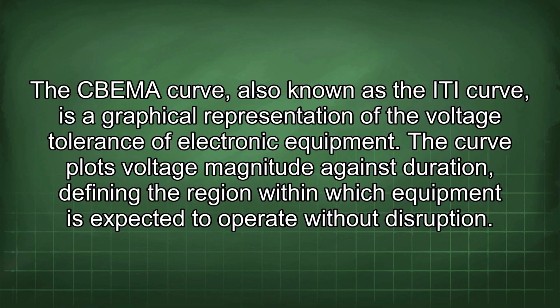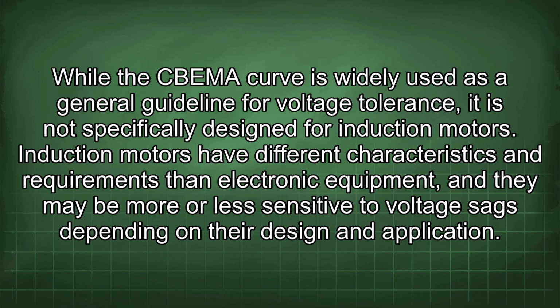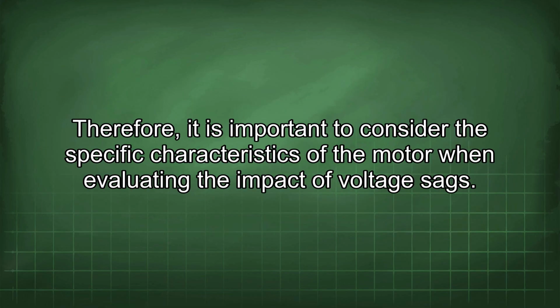The CBEMA curve, also known as the ITI curve, is a graphical representation of the voltage tolerance of electronic equipment. The curve plots voltage magnitude against duration, defining the region within which equipment is expected to operate without disruption. While the CBEMA curve is widely used as a general guideline for voltage tolerance, it is not specifically designed for induction motors. Induction motors have different characteristics and requirements than electronic equipment, and they may be more or less sensitive to voltage sags depending on their design and application. Therefore, it is important to consider the specific characteristics of the motor when evaluating the impact of voltage sags.